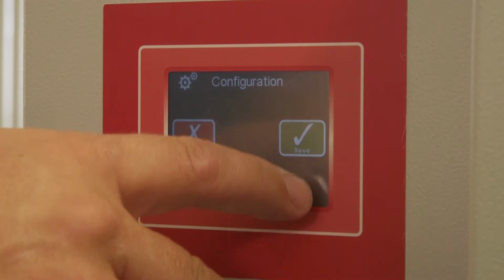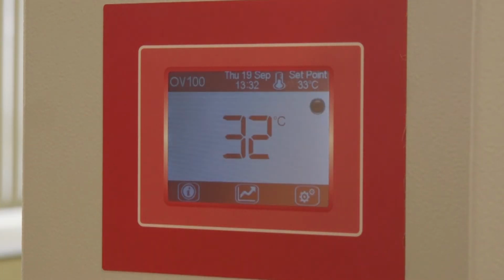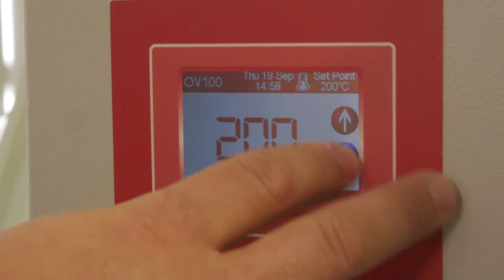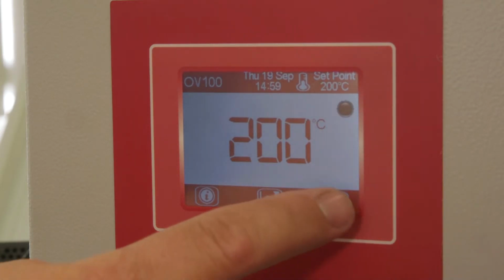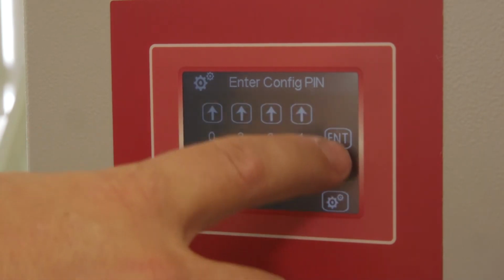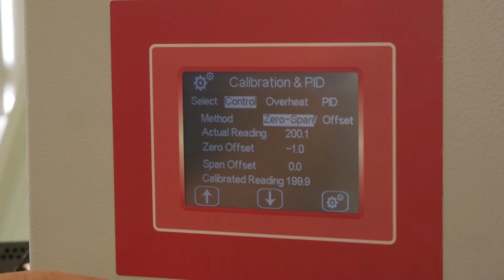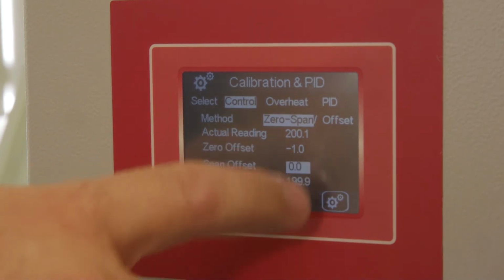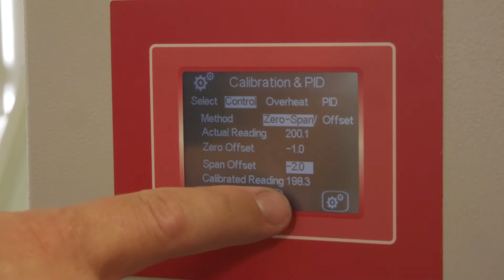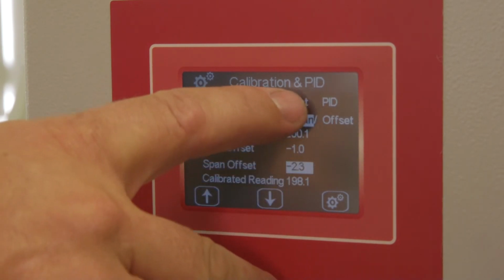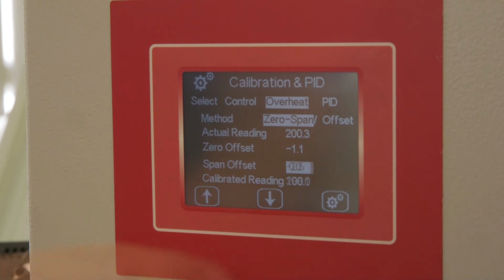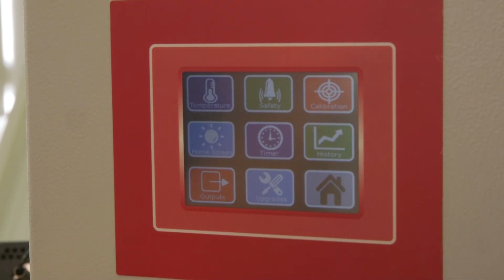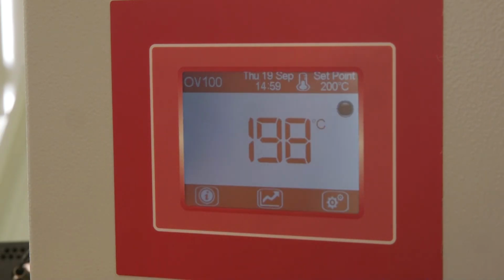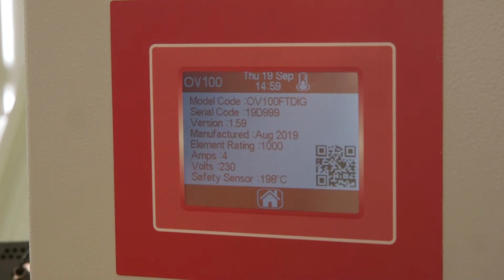To accept these changes, press the Config icon, then Home, and accept these changes. Now change the set point to the maximum set point. Enter the password 0381 with the up and down keys and press enter. Press the calibration and PID section, then highlight the control sensor. Press the zero span feature and then highlight the span value. Using the up and down keys, an offset is applied and the calibrated value is shown on the lower part of the screen. This must also be repeated for the overheat sensor. To accept these changes, press the Config icon, then Home, and accept these changes. The oven will now apply a linear calibration between the zero and span settings.